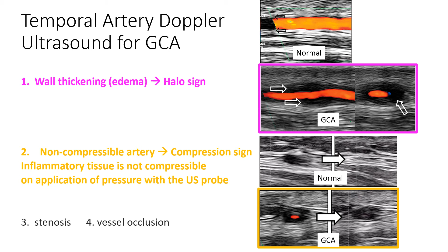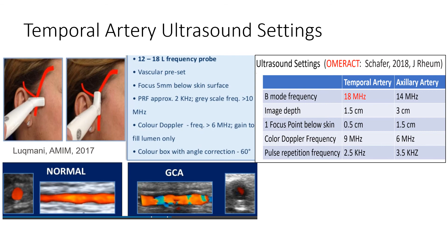For temporal artery ultrasound, a 15 to 18 megahertz linear array transducer focused 5 millimeters below the skin is recommended. The color Doppler frequency is 6 to 9 megahertz with gain to fill the lumen. The pulse repetition frequency is 2 to 2.5 kilohertz. Ultrasound has the advantage of being non-invasive, and on meta-analysis, the sensitivity varies from 68 to 77%.